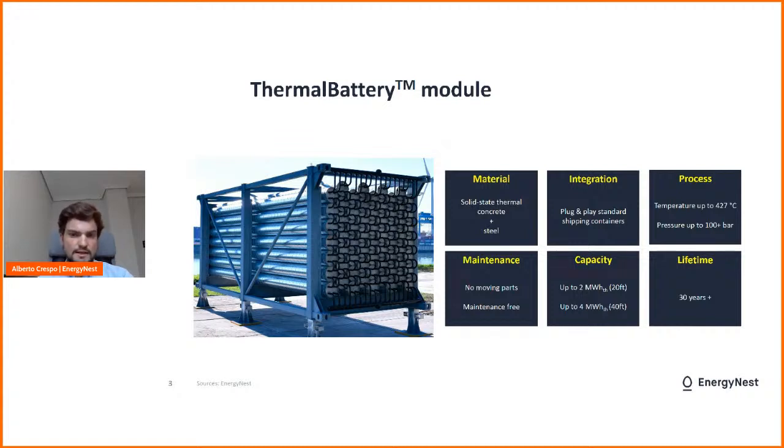The integration is a plug and play installation of this standard module simply by welding a couple of welds on top and at the bottom of the module. The process can handle up to 427 degrees because of the usage of carbon steel for economic reasons, and can handle pressures above 100 bar. This does not prevent us from tying into processes that are above these 427 degrees, for example, in waste heat recovery. That is perfectly manageable.